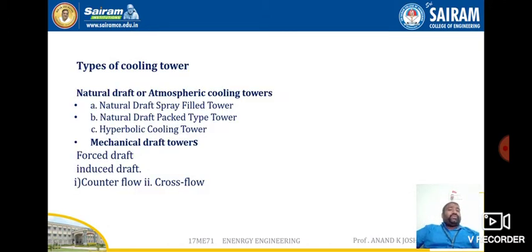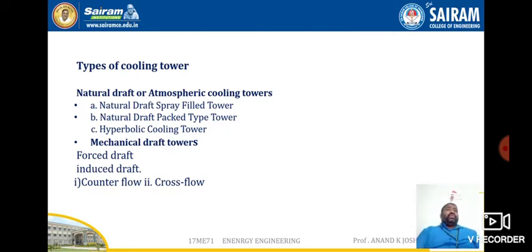Let us now discuss cooling towers and cooling ponds. Cooling towers are desired when precise control of water temperature is required, the space occupied by the cooling system is a considerable factor, and the plant is situated near the load center but far from adequate natural water sources. The rate of evaporation in a cooling tower depends on: the amount of water surface area exposed, the time of exposure, and the relative velocity of air passing through the droplets.